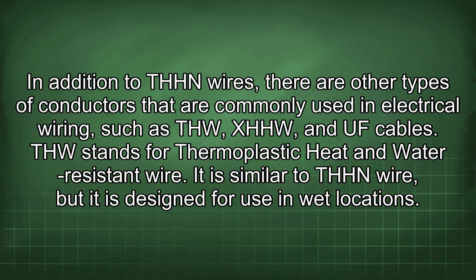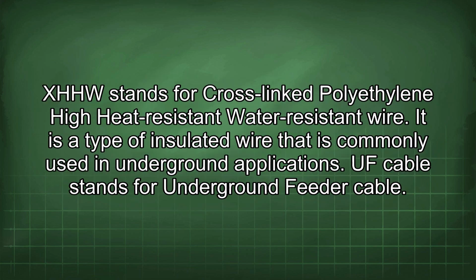THW stands for thermoplastic heat and water-resistant wire. It is similar to THHN wire, but it is designed for use in wet locations. XHHW stands for cross-linked polyethylene high heat-resistant water-resistant wire. It is a type of insulated wire commonly used in underground applications.